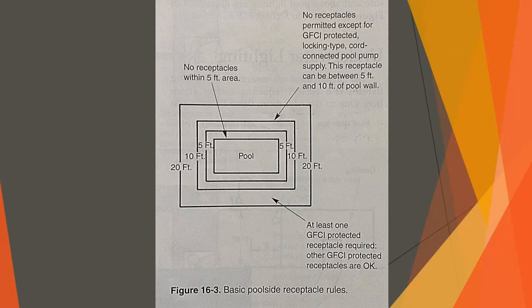Receptacles. The only receptacle permitted by the NEC to be located within 10 foot of a pool wall is a receptacle for a cord connected swimming pool pump. The pool pump receptacle must not be any closer than 5 foot from the pool wall. Further, the NEC requires that a minimum of one 120 volt GFCI protected receptacle be located between 10 foot and 20 foot of the pool wall for use of cord connected devices.